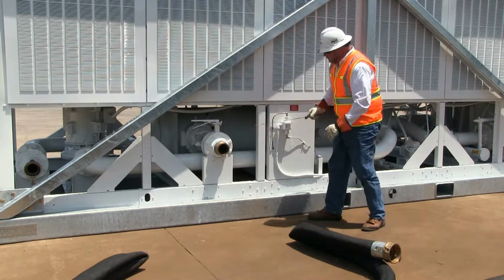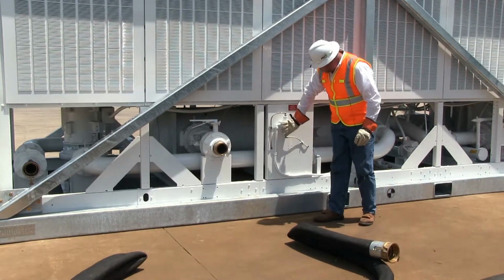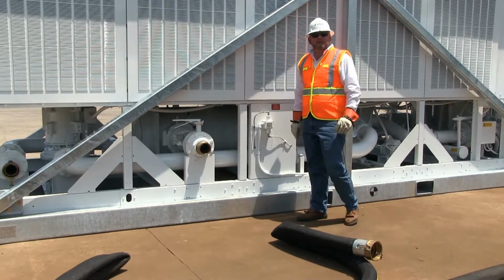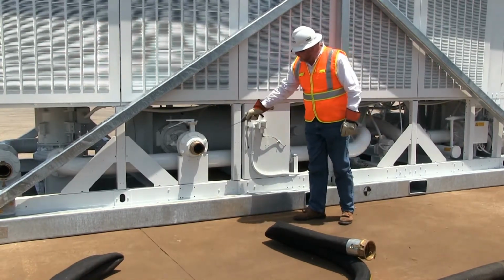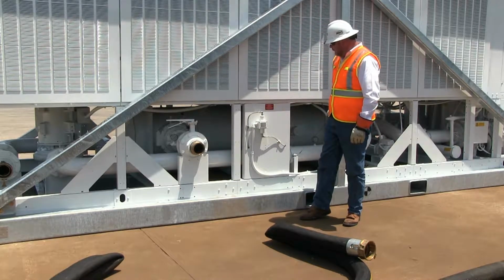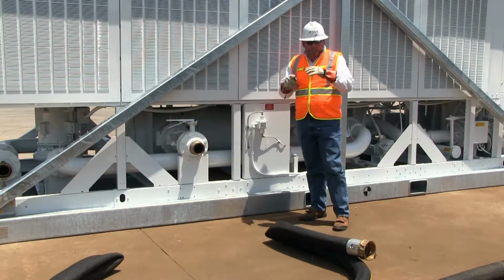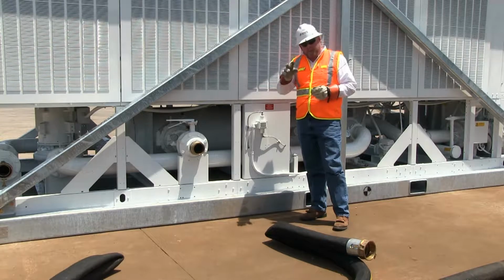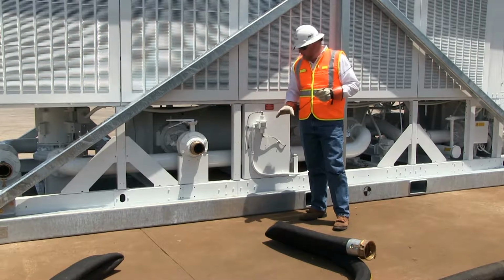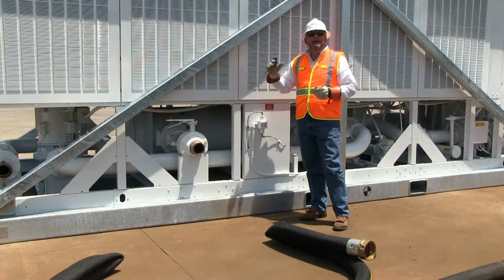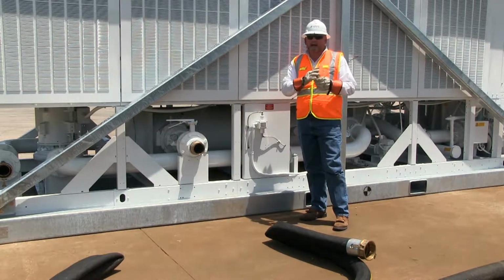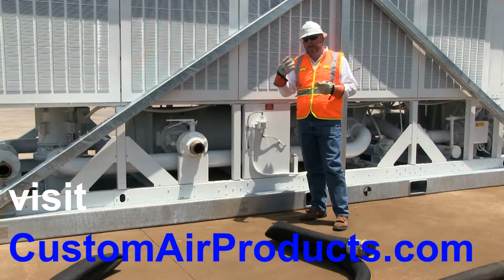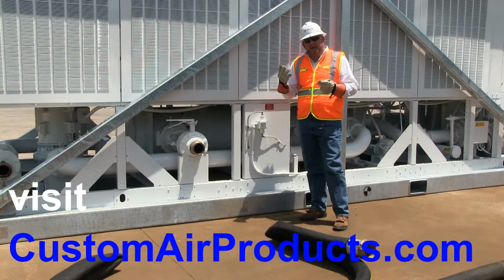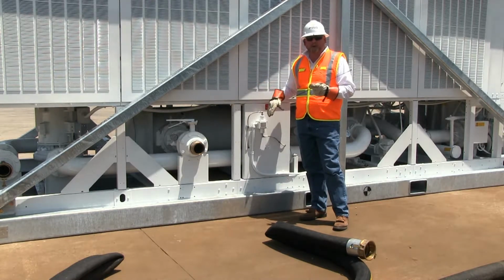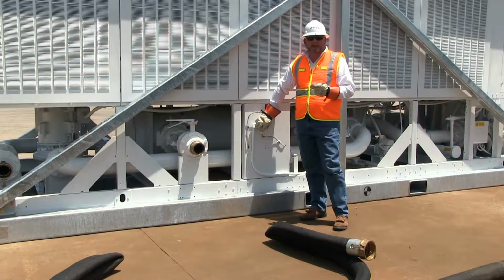The last item I want to cover while we're in this shot is our differential pressure switch, or better yet known as our flow switch. There's a hose going across the low side of the barrel and the high side of the barrel. As long as there's differential pressure, meaning full water flow across the heat exchanger, that creates a pressure differential that makes the switch that proves and tells the chiller, I have flow, I'm safe to run. Anytime that we lose water, have air in the system, or any type of abnormality during the setup, we do not have differential pressure across there. This switch is a lifesaver and will shut down the chiller and await a service call.